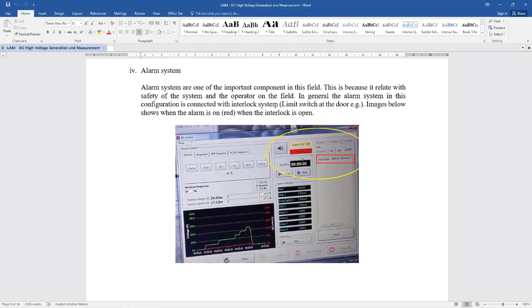In this display here, the alarm is on because we can see the interlock at the door, which indicates that the door is not properly closed. That's why the alarm is triggered. When the alarm is triggered, we cannot do the injection to the high voltage transformer. The next alarm is the emergency button. When we press the emergency button, it will automatically shut down the power and the alarm will still be on. That's why we cannot do injection. In order to do injection, we need to clear both of these faults first.